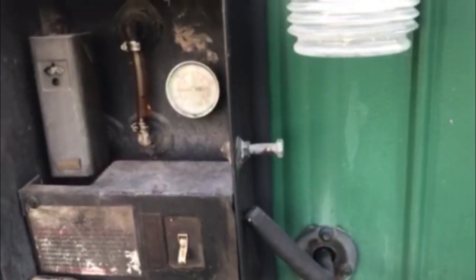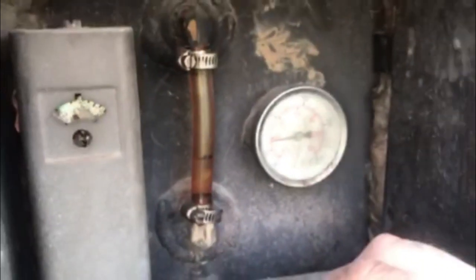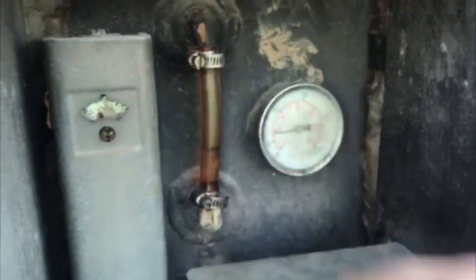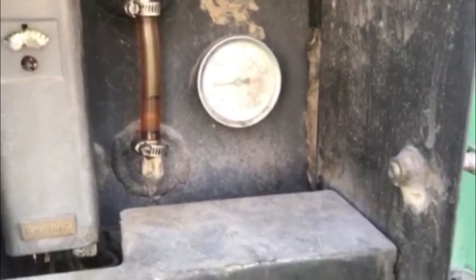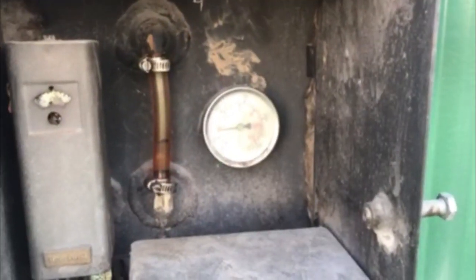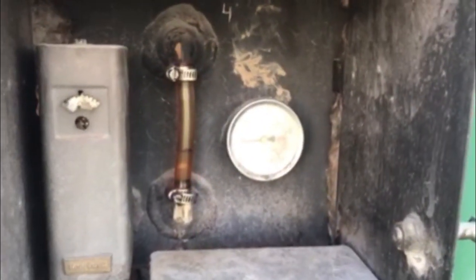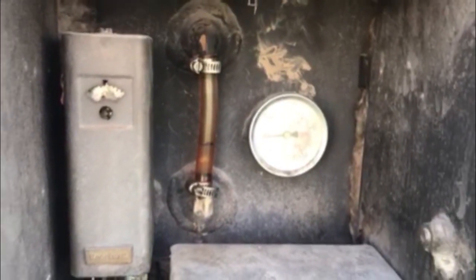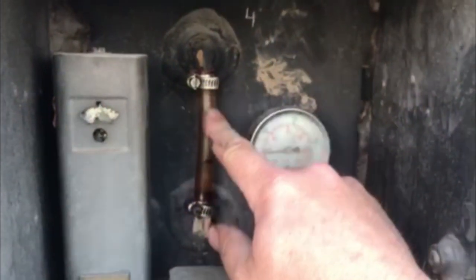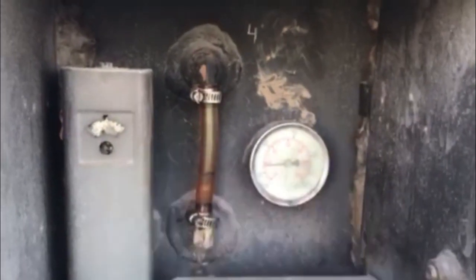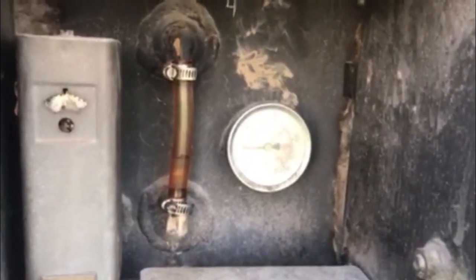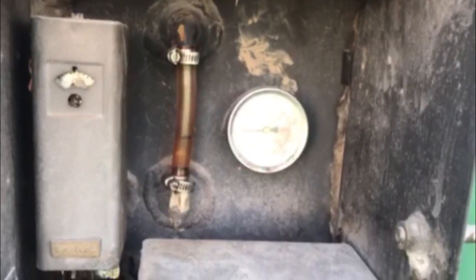My problem is that I have a water leak, so it's kind of hard to tell. I filled this up the other day and checked it. Usually before I fire it up, I fill it up, turn the pump on, and watch the water level for a while to make sure it's staying put. It dropped completely off the sight tube in 2 days, which is not good, especially when there's no fire going. Sorry again for the wind.